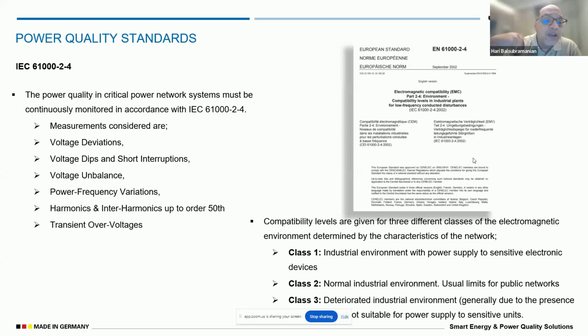61000-2-4, which is for equipment, talks about voltage deviations, short-term interruptions, voltage unbalance, and interharmonics up to the 50th order. EN50160 talks only about voltage harmonics up to the 25th order, and then the transient overvoltage. It can be classified as class 1, class 2, and class 3 as well, in 61000-2-4.